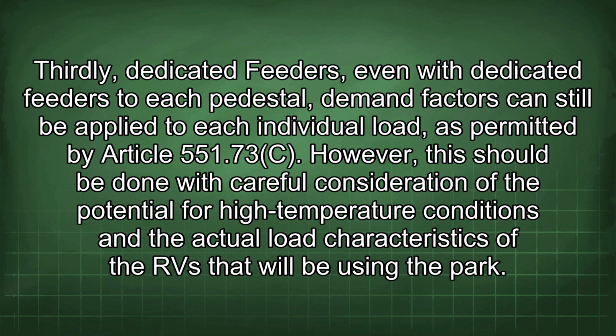Thirdly, dedicated feeders. Even with dedicated feeders to each pedestal, demand factors can still be applied to each individual load, as permitted by Article 551.73(C). However, this should be done with careful consideration of the potential for high temperature conditions and the actual load characteristics of the RV that will be used in the park.